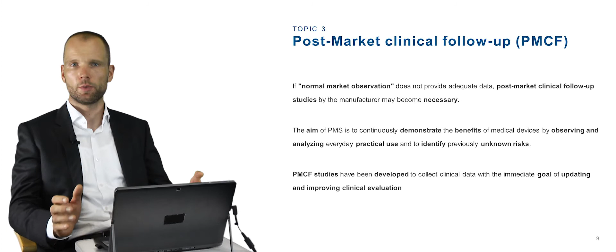If normal market observation doesn't provide adequate data, post-market clinical follow-up studies by the manufacturers may become necessary. The aim of the post-market clinical follow-up is to continuously demonstrate the benefit of the medical device by observing and analyzing everyday practical use and to identify previously unknown risk. Post-market clinical follow-up studies have been developed to collect clinical data with the immediate goal of updating and improving clinical evaluation. Now I'd like to talk about the connection between post-market surveillance, vigilance and post-market clinical follow-up.